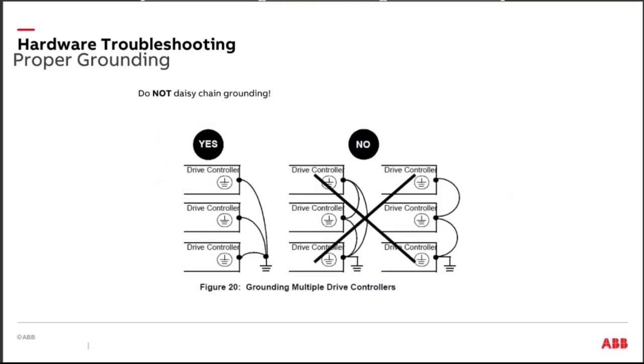I think grounding is one of the most underestimated things that we have with the drive. When you ground your drives, make sure that you're getting a good ground on each drive. You absolutely, positively cannot daisy chain. Cannot. You're going to be picking up noise from one drive and dumping it right into the next drive. That's not allowed. You can't do it.